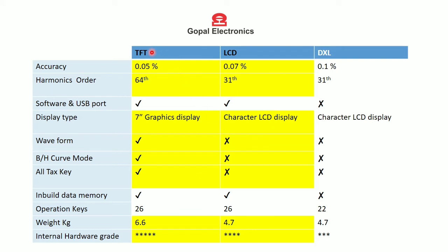Now I will highlight the advantages of the TFT model over the LCD model. The TFT model is more accurate. It can measure harmonics up to the 64th order, whereas the LCD model measures up to the 31st order. The graphical display is provided in the TFT model only, so it can show waveform and BH curve modes. The All Tax key is also exclusive to the TFT model, and as per hardware grade, the TFT model is leading.